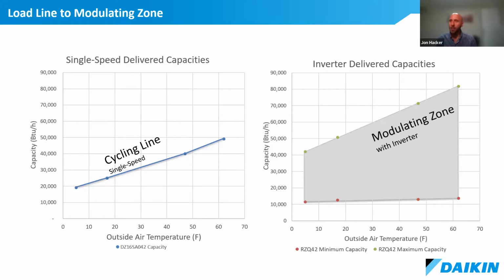We've got a question about what the COP is while modulating. It's a really great question. I've got some graphics to cover that, but basically the idea is that COP will vary depending on the speed of the compressor. Typically, if we're operating at a slower speed, COPs are generally going to increase at that same outdoor condition compared to operating the compressor at a higher speed.